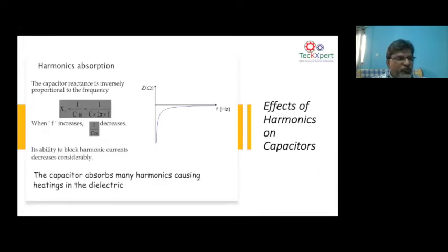Okay, now whenever you have power factor problems, it is natural that you put capacitors in the network. And then what happens? It's a very common thing. When you put a capacitor in the network, the first thing that happens is the capacitor will absorb the harmonics if they are there in the network, because the capacitor impedance is 1 by 2 pi FC, as you all know. The higher the frequency, the lower the impedance, so the capacitor will absorb the harmonics.